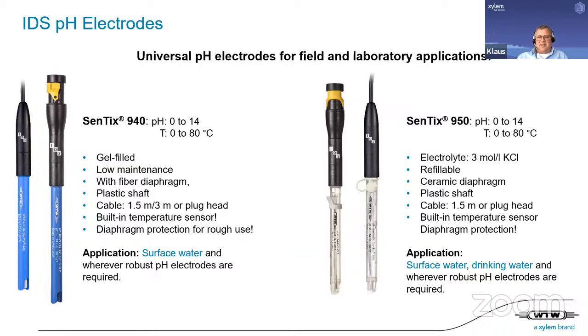The next electrode is the SenTix 950, which is a liquid-filled electrode. It's also rugged. It has a plastic shaft, and it also has this nice protection around the membrane. This one is, for instance, also used for field work. So you can use it in drinking water applications when you go down to the well and want to measure pH. Then, of course, this is a good electrode in this application, and that means surface water can also be measured. It's a liquid-filled, robust electrode that requires, of course, a refill of the KCl from time to time.